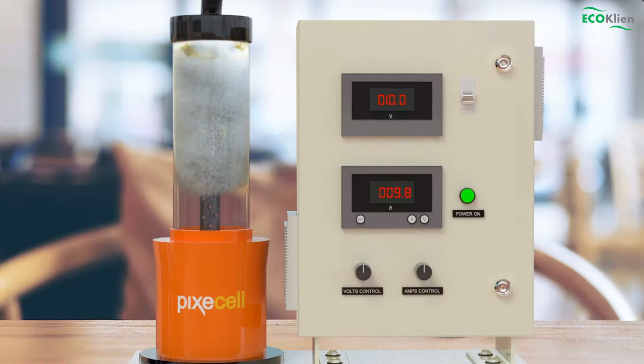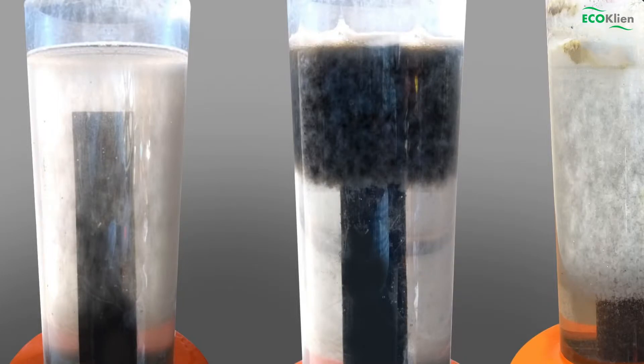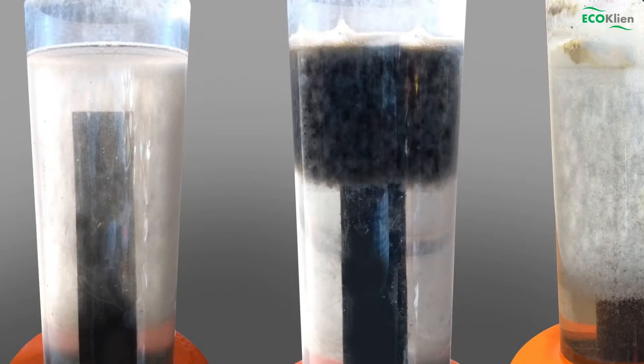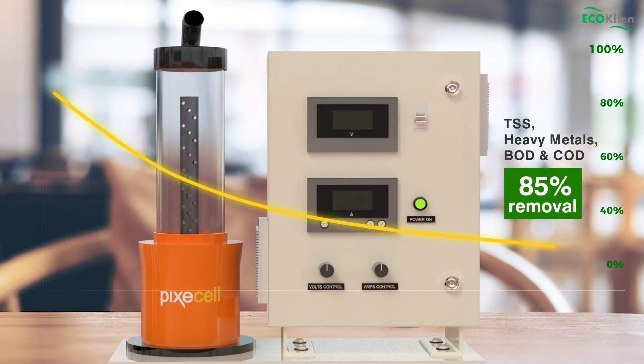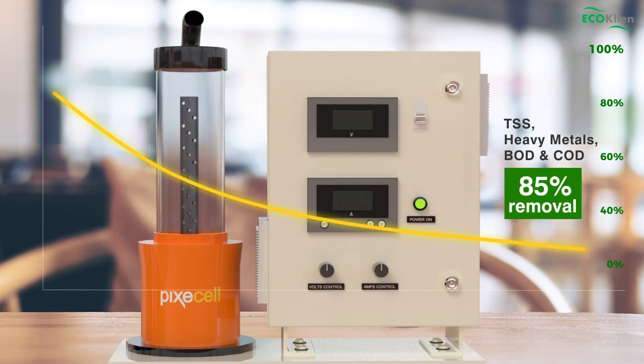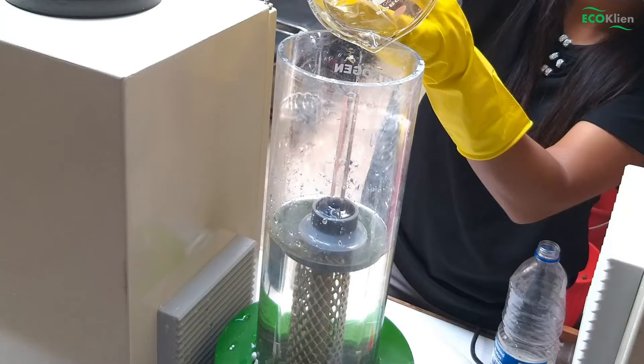Electrolysis of the effluent in the reactor ensures free flow of electrons, destabilizing the surface charges on suspended solids, heavy metals, and organic compounds, forming large flocs and finally settling down. This provides a clear liquid with 60 to 85 percent removal efficiency of TSS, heavy metals, BOD, and COD.